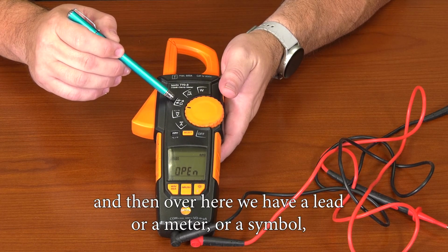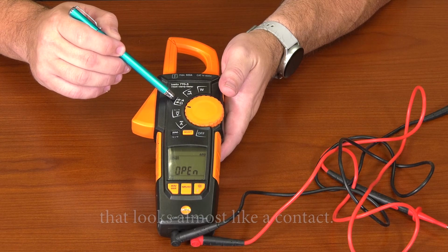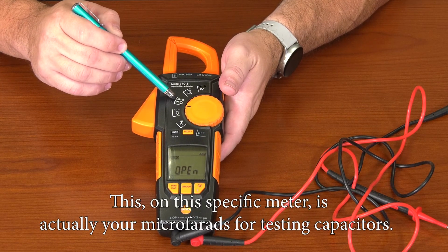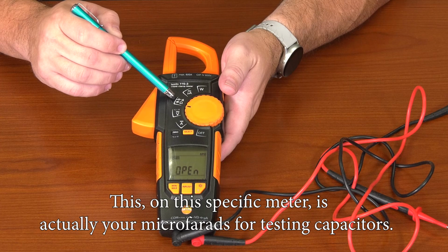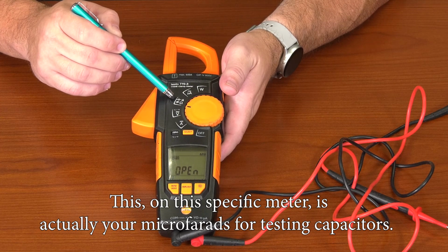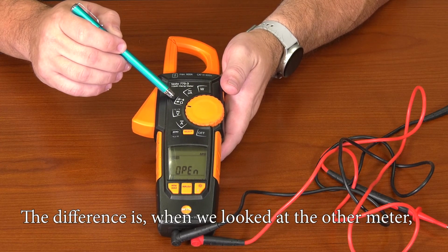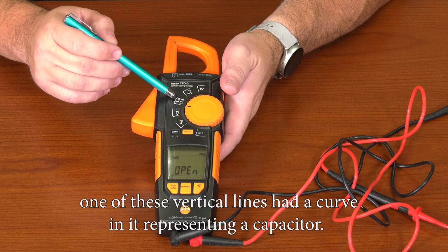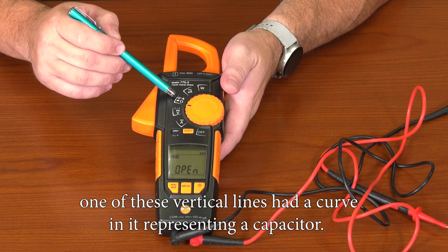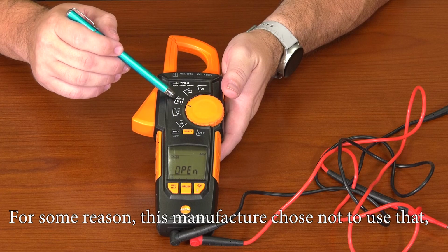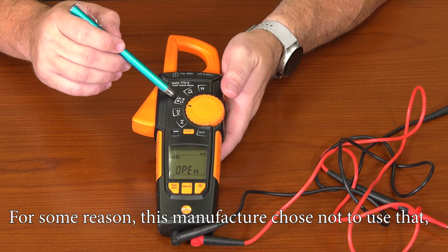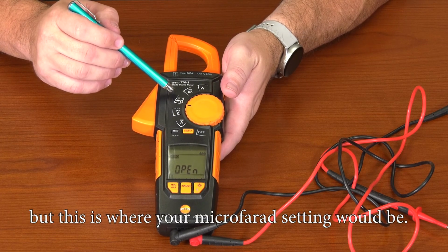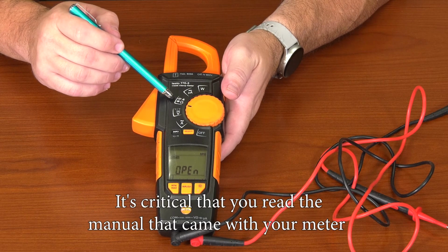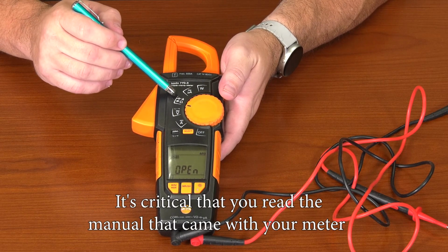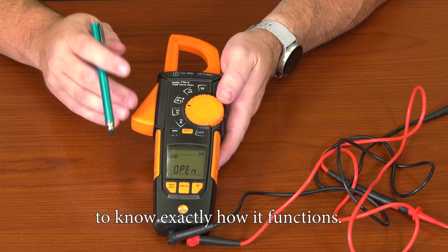And then over here we have a symbol that looks almost like a contact. This on this specific meter is actually your microfarads for testing capacitors. The difference is when we looked at the other meter, one of these vertical lines had a curve in it representing a capacitor. For some reason this manufacturer chose not to use that, but this is where your microfarad setting would be. It's critical that you read the manual that came with your meter to know exactly how it functions.